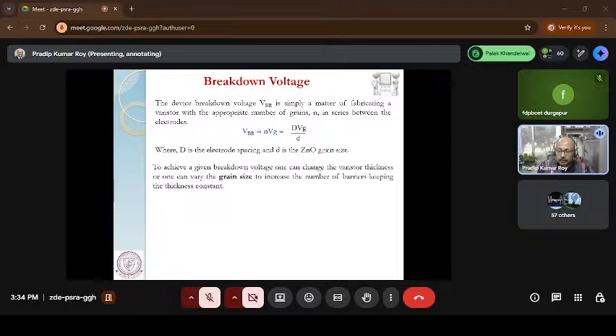Otherwise, if the grain boundaries increase, then the rating of the block also increases. So how do we increase the rating of the block? The number of grain boundaries depends upon D, where capital D is the thickness of the block and small d is the diameter of the grain size. So if I reduce the grain size, the number of grain boundaries will increase. If the number of grain boundaries increases, a higher breaking voltage is required to pass the electron from one grain to another grain. That means my rating of the block is increasing. So for the same height and same thickness, if I want to increase the rating of the block, the dimension of the grain size should be reduced.